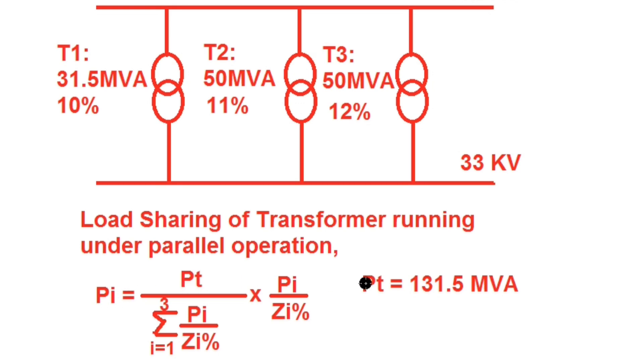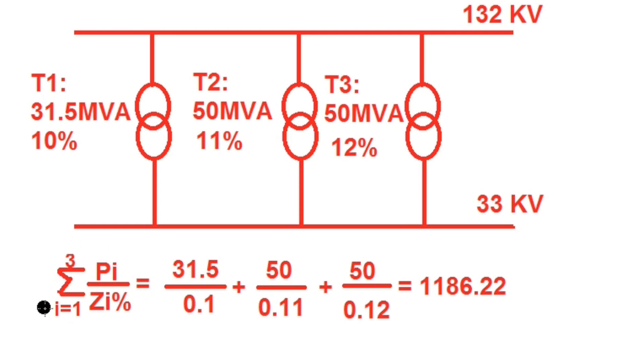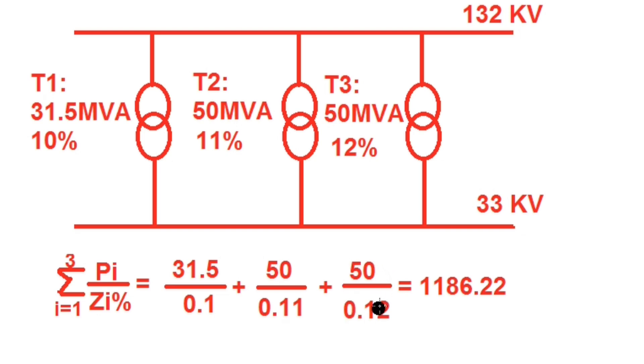We first calculate the summation of Pi divided by percentage impedance for i = 1, 2, 3. For transformer 1: 31.5 divided by 0.1; for transformer 2: 50 divided by 0.11; and for transformer 3: 50 divided by 0.12. The total summation comes to 1186.22.